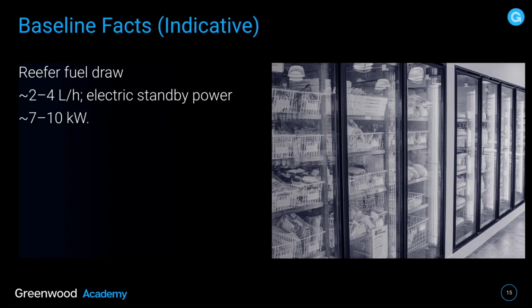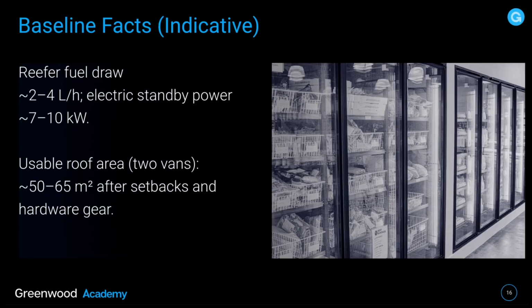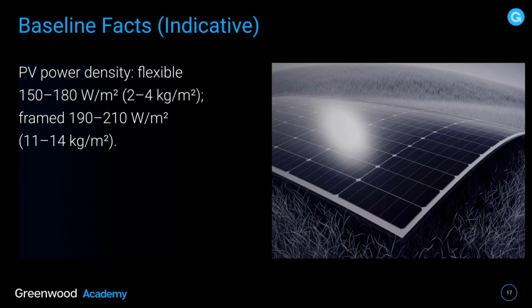Baseline facts, indicative. A reefer fuel draw is anywhere between 2 to 4 litres per hour, for electrical standby power, which equates to 7 to 10 kilowatts. The usable roof area, with 2 vans, is 50 to 65 metres squared after setbacks and hardware gear. PV power density, flexible: you're looking at panels of 150 to 180 watts per metre squared, so 2 to 4 kilograms per metre squared. Framed: 190 to 210 watts per metre squared, and 11 to 14 kilograms per metre squared.